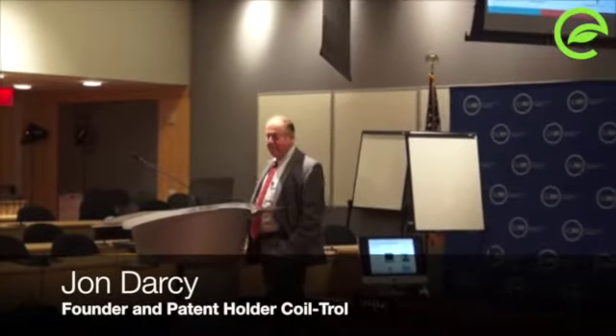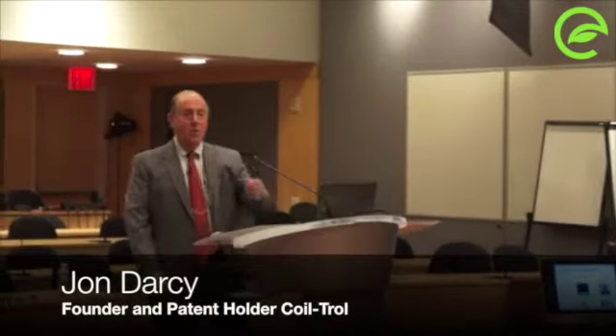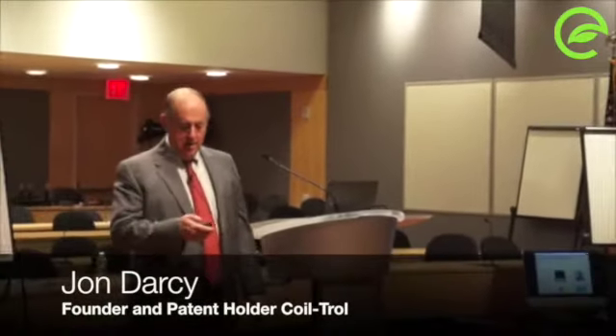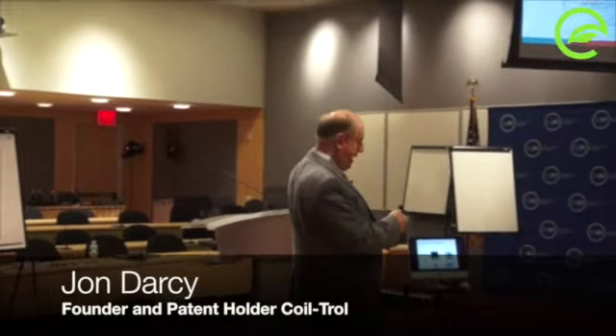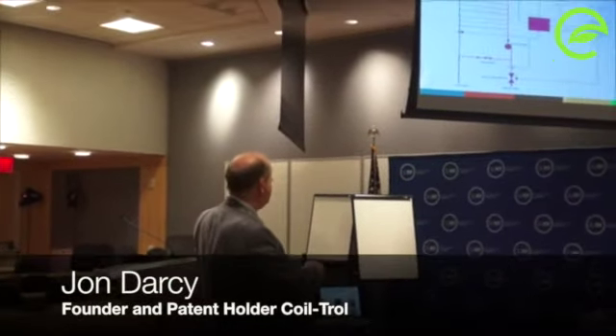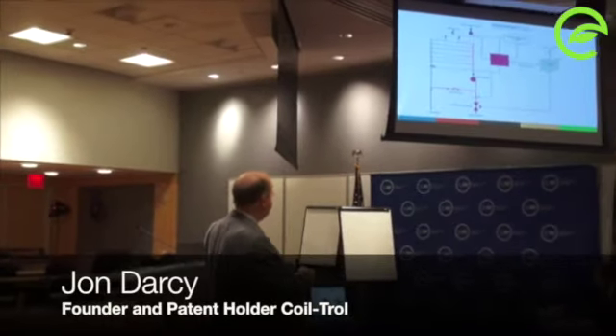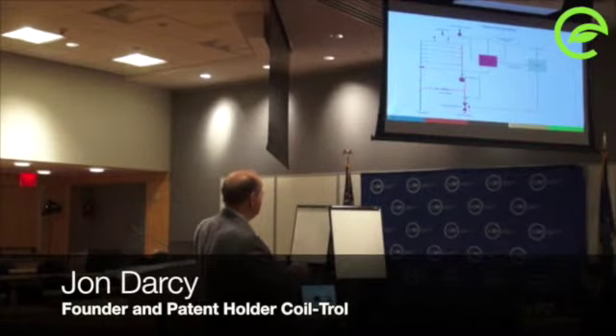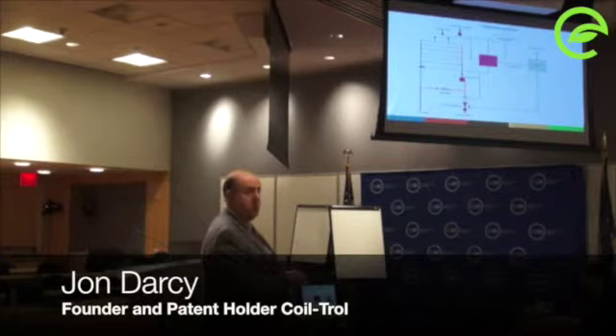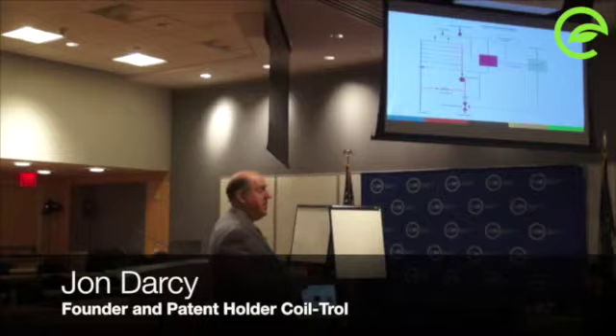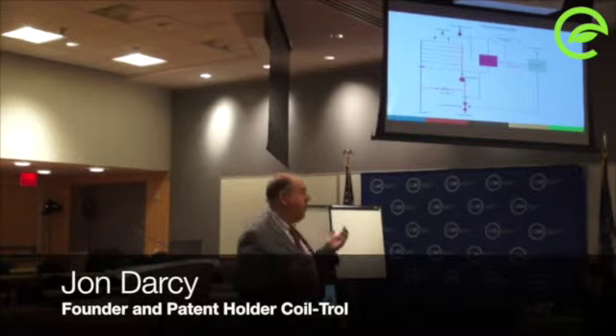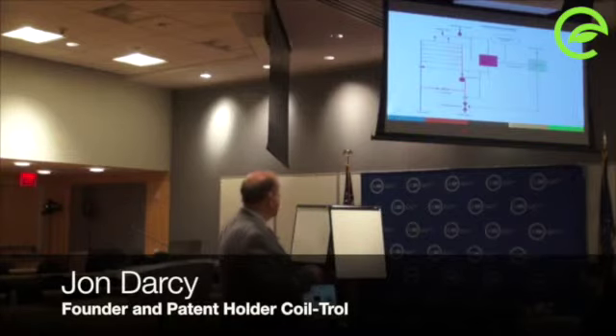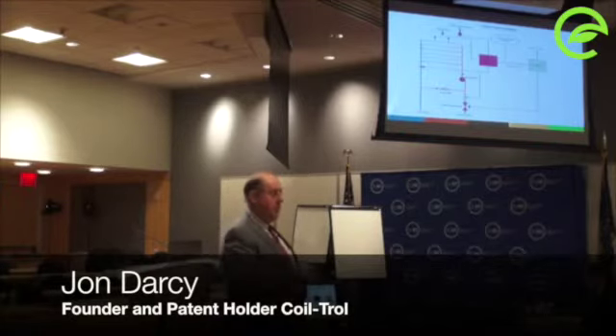Okay. And John, the high delta T? What's that? We are only injecting cold water as much as you need. Yeah, it just injects cold water coming in, warm water coming out. Yeah, this is coming in at 45 or 48 from your plant, right here. And then it's mixing with the water coming back from the coil, which may be 55 or 58. And then going into the coil, it might be 56, 54, depends on how much. As that valve opens and lets water out of the system, this then lets cold water into the system. Whatever goes out can come in.